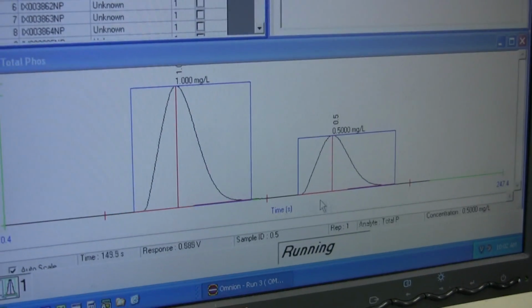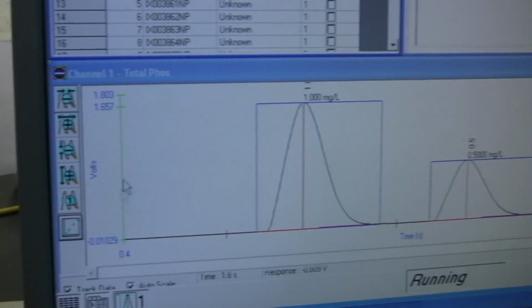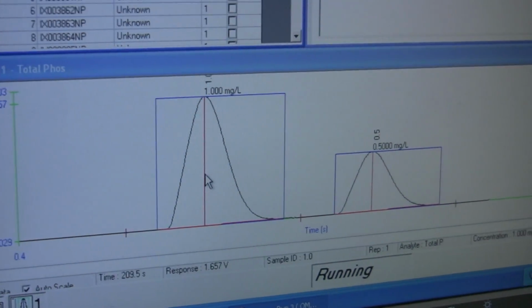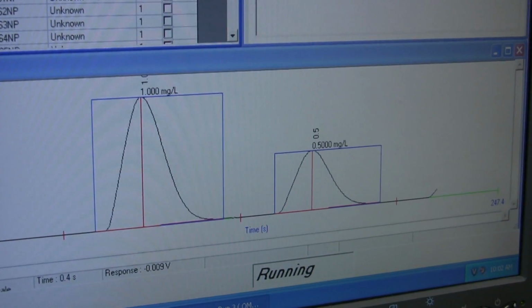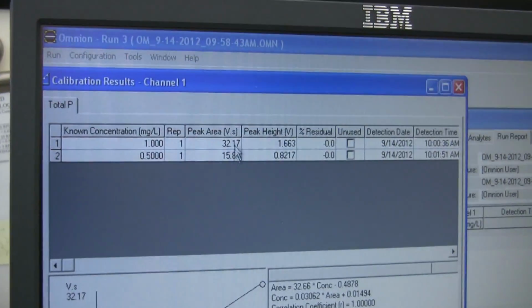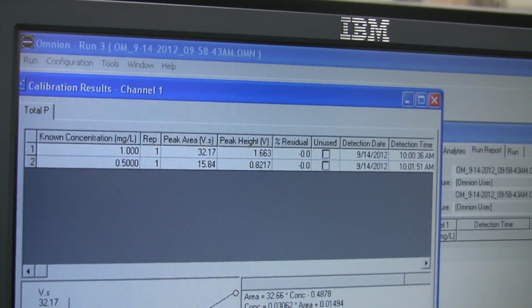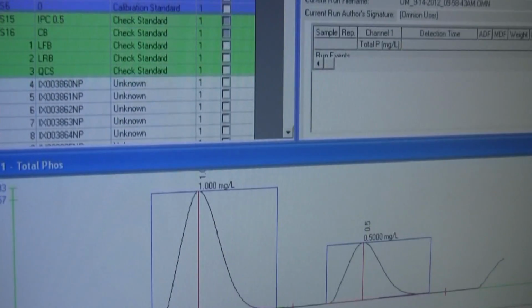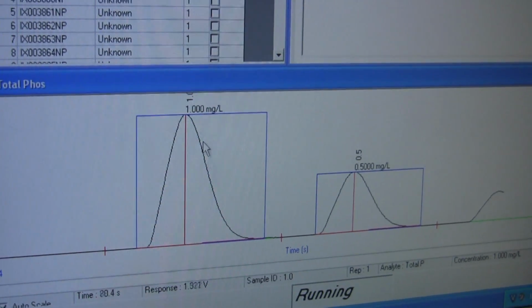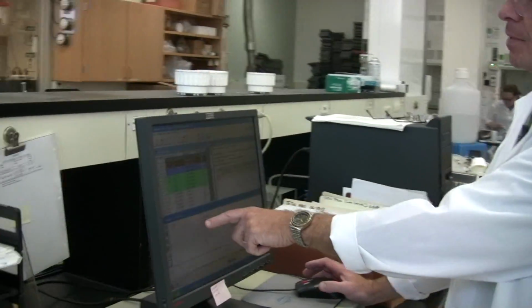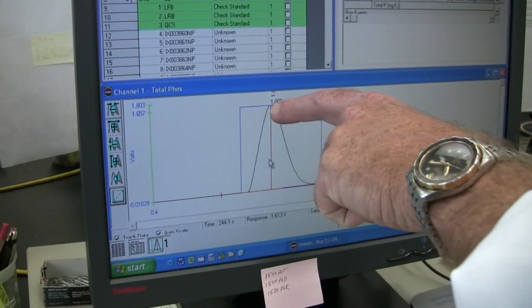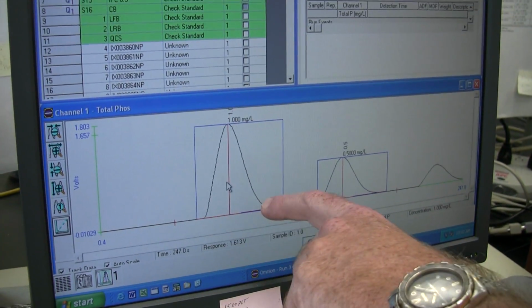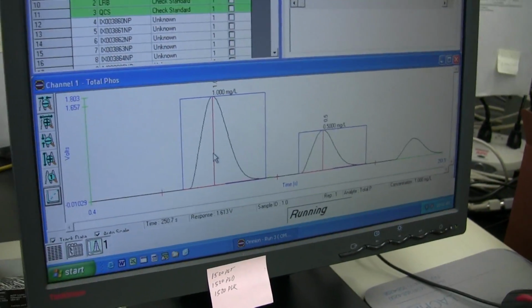On the X here we have time in seconds, and then we have volts. So basically the area is plotted as volts per second, or whatever it calls it. So it figures out a peak area based off that, and the peak area, being this area, is what it's figuring out. Voltage is related to the color of the water? Right, it's the absorbance. The easiest way to describe it is the peak height. This isn't really 0 volts and this is 10, but it's something like that. The voltage would be the measurement to the top, and then your seconds is how wide it is. But this is a reflection of the absorbance of the water.